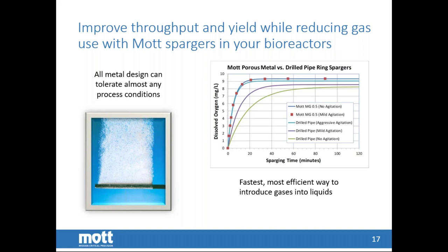Your gas to liquid transfer efficiency is much higher with the porous metal. The graph on the right shows that the porous metal sparger, with or without agitation, they're pretty much on top of each other, and it also gives you the best gas to liquid transfer efficiency. When you get to a drill pipe with no agitation, you can see it takes a lot longer to get up to, in this case, the dissolved oxygen level of 8, and it's difficult with a drill pipe to get much higher than 8.